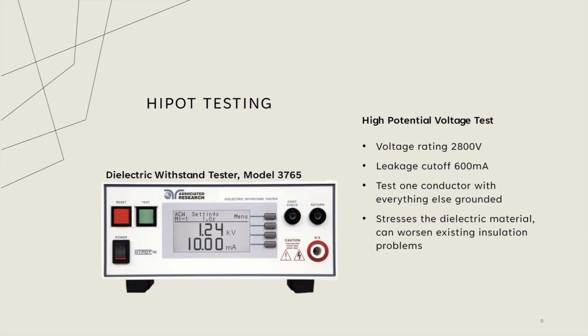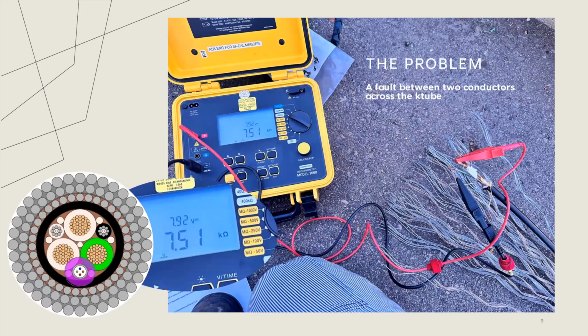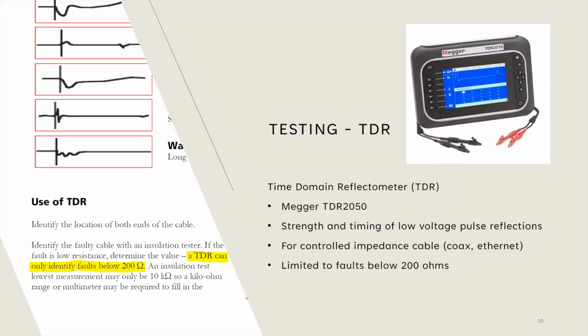So we found a problem while we were doing this test, and using a megger, we tested the resistance of the fault, which was across these 2 conductors adjacent to that uninsulated K-tube. So that fault kind of varied depending on the testing conditions between about 5 and 20 kilo ohms.